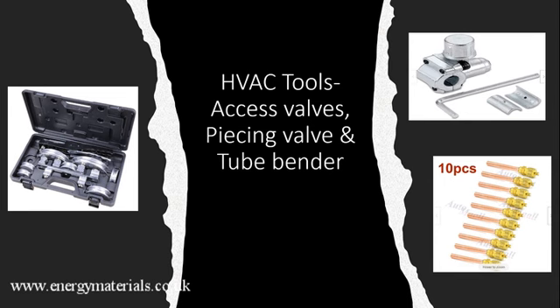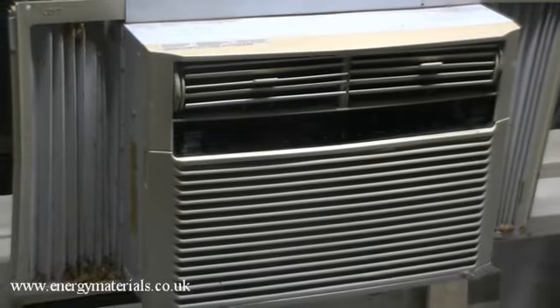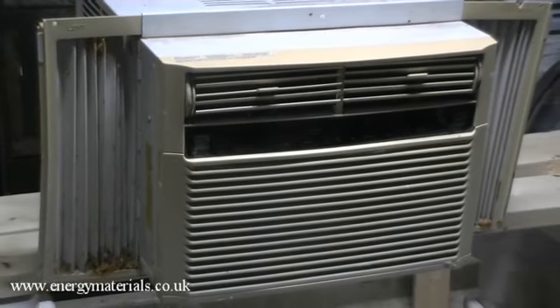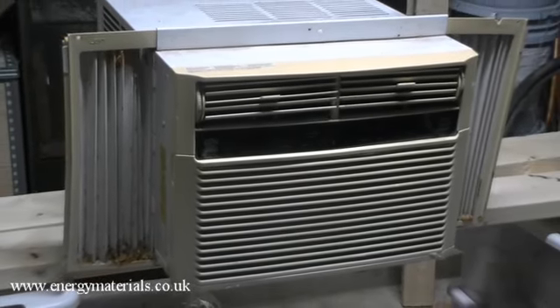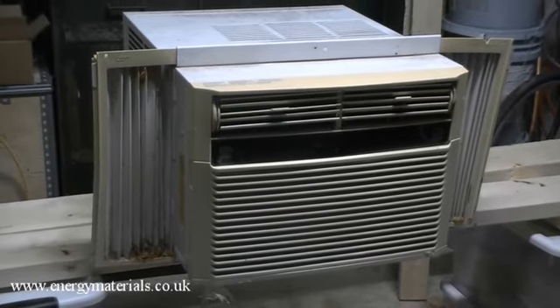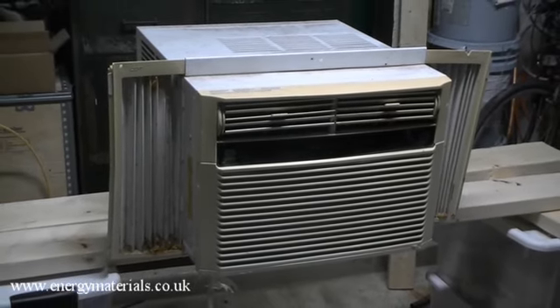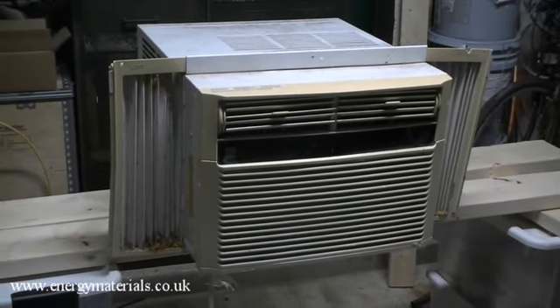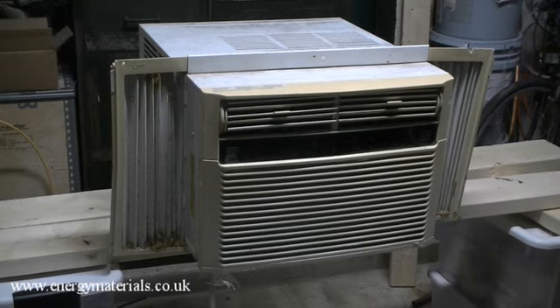And finally, some other tools. We're going to use a rather nifty tube bender for HVAC. And also, as the window AC unit doesn't have access valves, we need to add those. So we have some access valves and a piercing unit. So this is the window AC unit that we're going to modify. It's a standard 110 volt window AC unit, 12,000 BTUs, and runs on refrigerant R410A.